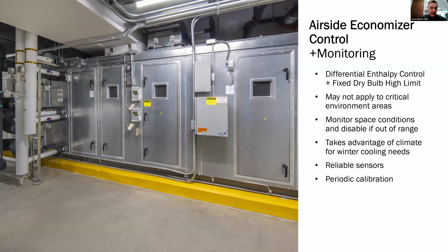Airside economizer. Economizer is usually a no-no in the museum setting, but as I said, this museum had very lofty sustainability goals. So we explored airside economizer control plus monitoring. We looked at spaces that were less than critical and implemented a sequence that used economizer but monitored space temperature and humidity and the impact of economizer on that. Economizer functionality would be in place, but if monitored space humidity and temperature got out of range for a period of time, economizer function would be disabled. That way, the system would have a chance to get back into range. So that's one way to do it in a museum setting.